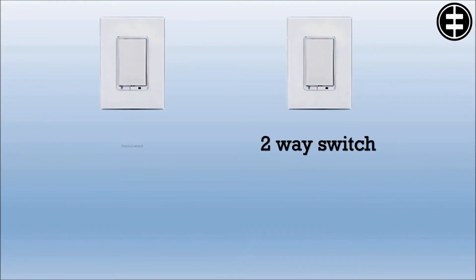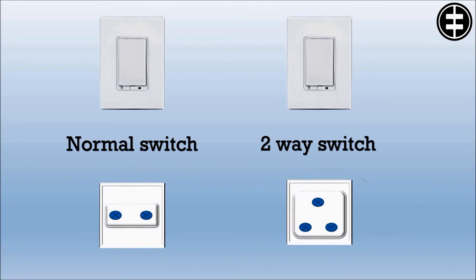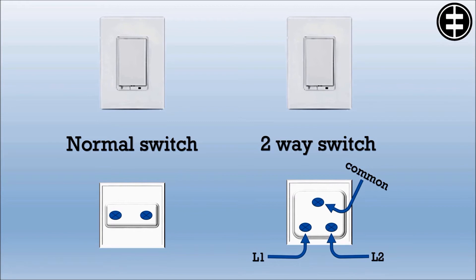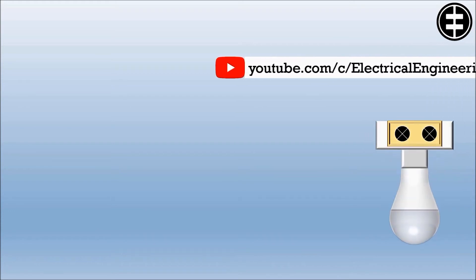The two-way switch looks the same as a normal switch from the front, but from the back side you will find three terminals: one is called common, and the others are called L1 and L2. Consider the common as an input and L1 and L2 as outputs. With a multimeter, you will find the common is always closed with one side and open with the other. By flipping the switch, the status of the two contacts changes, allowing you to change the current flow each time you switch.